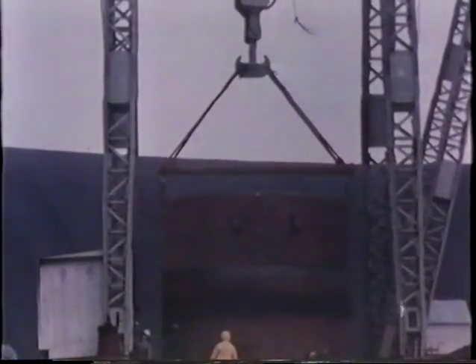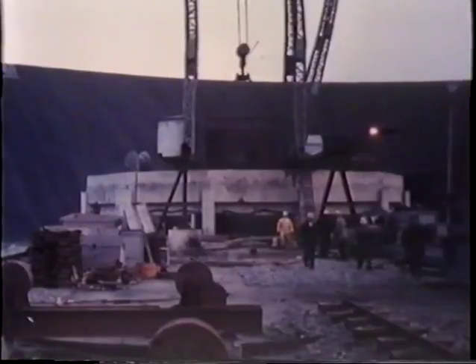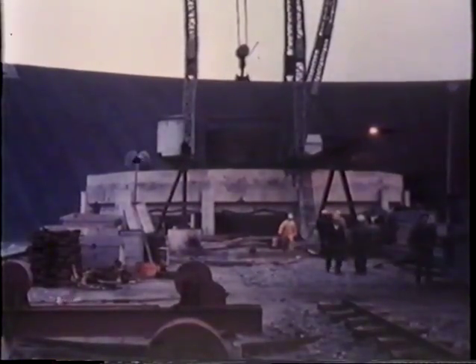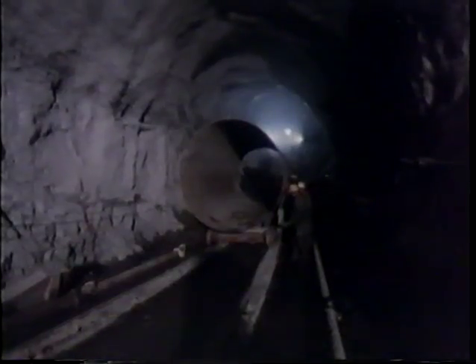All components were subject to rigorous chemical analysis and distortion tests. Each section, 10 meters in length, was welded on site from 8 semicircular plates. These double automatic welds were checked ultrasonically using radiography as well when in doubt. The sections, the heaviest weighing 48 tons, were lowered in turn through the intake. The total penstock weight is about 2,500 tons.